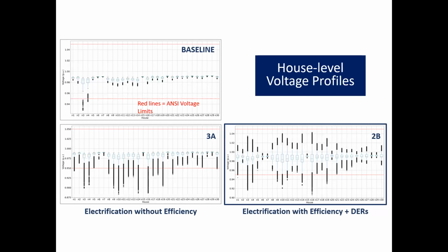If you look at scenario 3A, as we electrify the HVAC and the water heater, the electricity consumption increases and lowers the voltage profile compared to the baseline scenario. There are many more instances of undervoltage in scenario 3A that we could clearly see compared to the baseline scenario. Now, if you look over at scenario 2B on the right-hand side, the addition of PV is responsible for the instances of higher house voltages, mainly during periods of PV production, but the overvoltage is still within the permissible limits of 1.05 for all the homes. Okay, next slide, please.